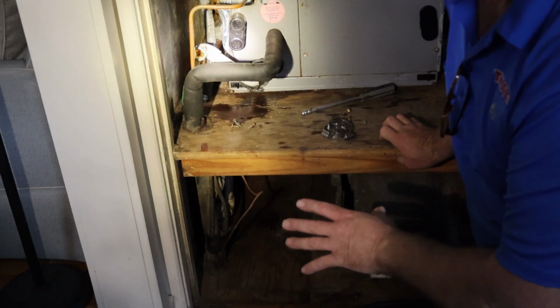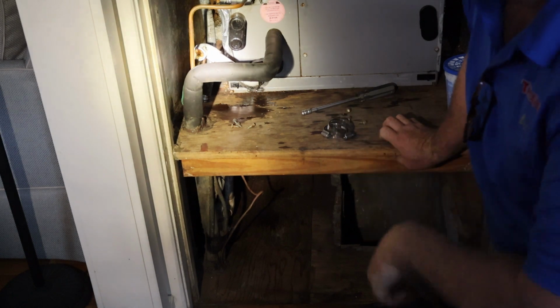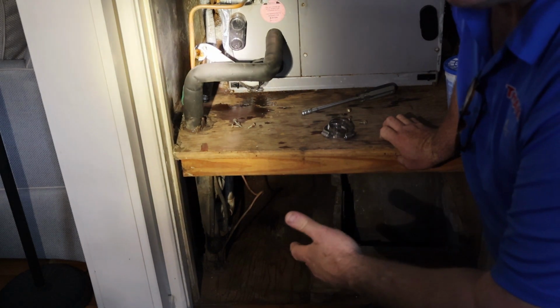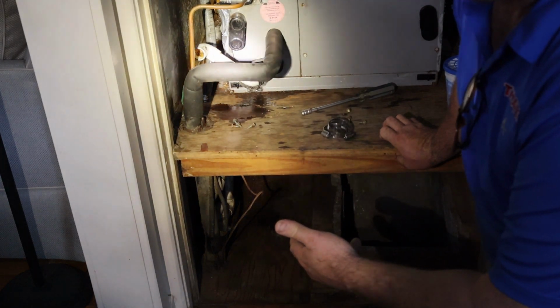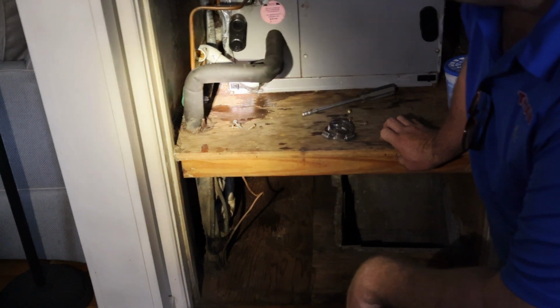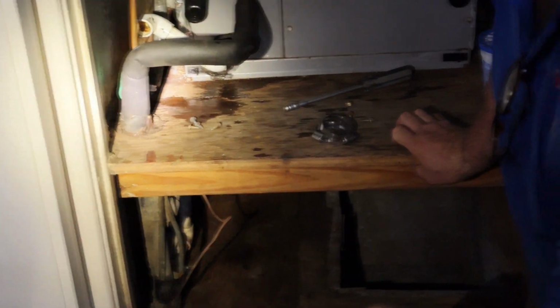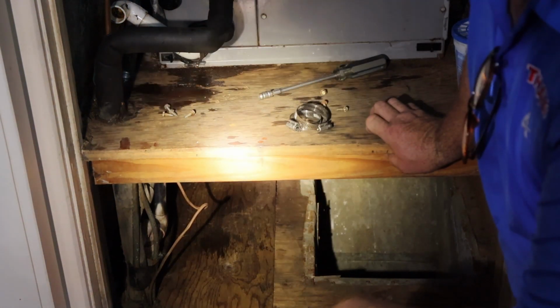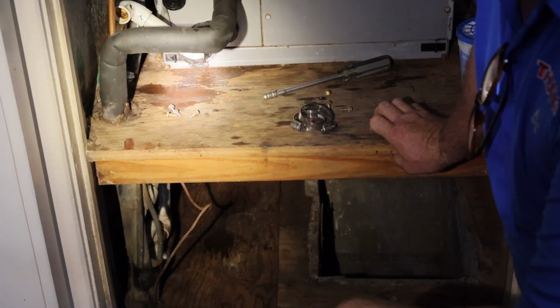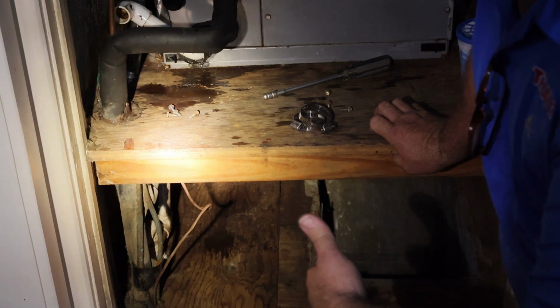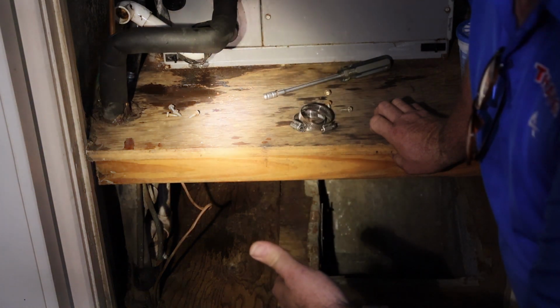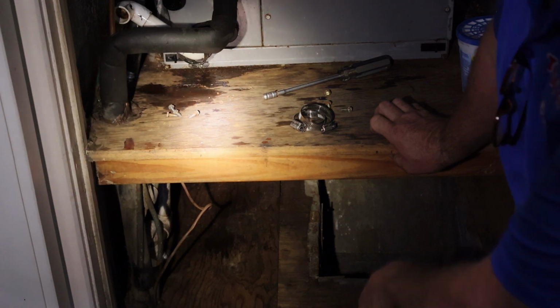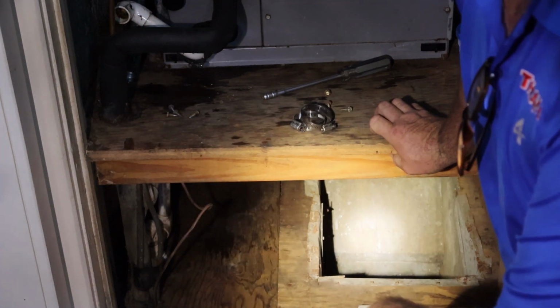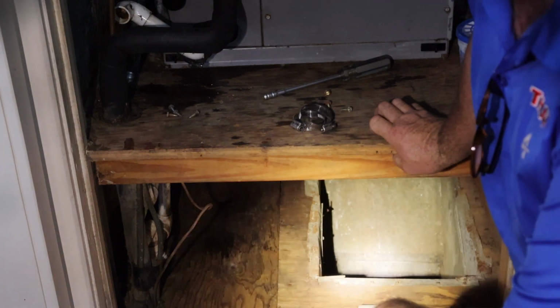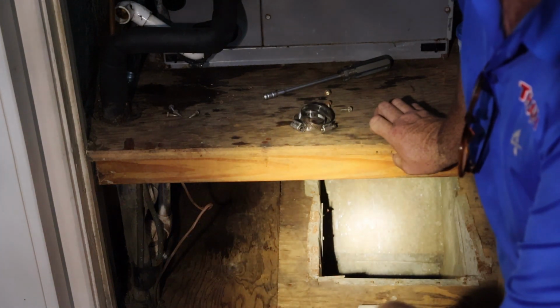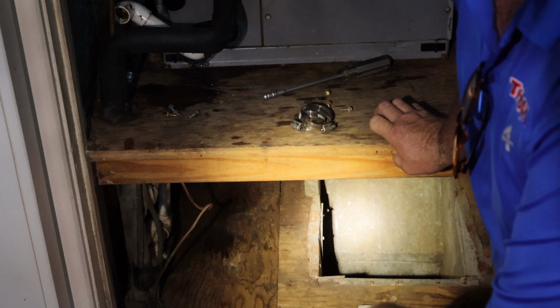Dave's in the process of gluing a joint. He's letting it dry, and then he'll finish hooking the drain up. But one thing a technician needs to be aware of, and it's probably one of the most important parts of your job, is to make sure we have some safety of some sort to prevent material damage, floor damage, anything that can get wet and cause a problem. We need to make the customer aware of that. Now this one, the way it's designed, if you can see the hole down at the bottom, it's very challenging to get a safety pan underneath it. It's possible, but very challenging. But we do need to make the customer aware that they need some type of safety.